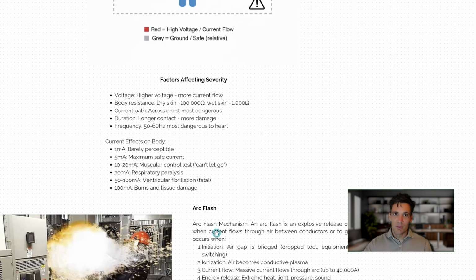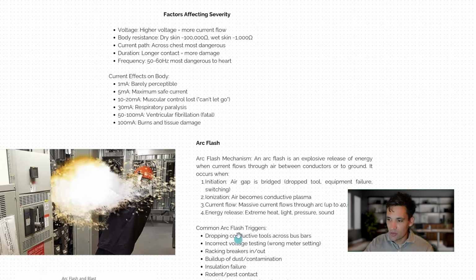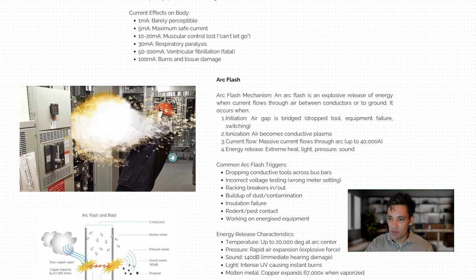The other way that people can get hurt with electricity is through arc flash. Arc flash is an explosive release of energy when current flows through air between conductors, or to the ground. That's what lightning is. That's where you see that bright light, the explosion. That is current flowing through an air gap, which causes the air to ionize and become conductive plasma. Current flows through it and huge amounts of heat, light, pressure, and sound are released. That's why you hear the massive explosion when there's lightning.